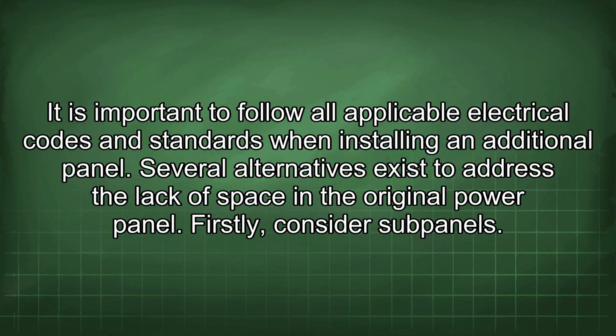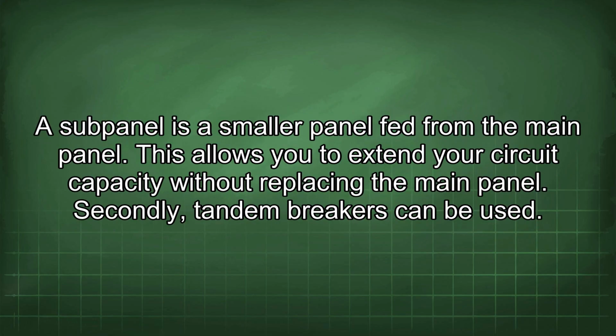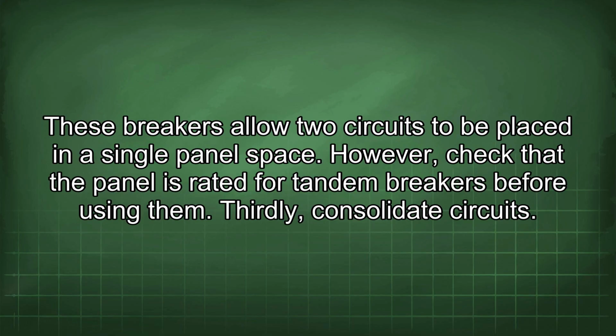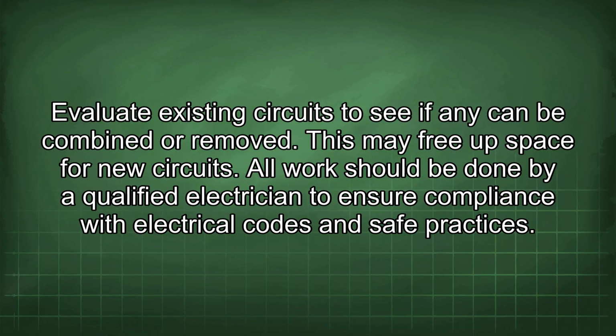Several alternatives exist to address the lack of space in the original power panel. Firstly, consider subpanels. A subpanel is a smaller panel fed from the main panel. This allows you to extend your circuit capacity without replacing the main panel. Secondly, tandem breakers can be used. These breakers allow two circuits to be placed in a single panel space. However, check that the panel is rated for tandem breakers before using them. Thirdly, consolidate circuits. Evaluate existing circuits to see if any can be combined or removed. This may free up space for new circuits. All work should be done by a qualified electrician to ensure compliance with electrical codes and safe practices.